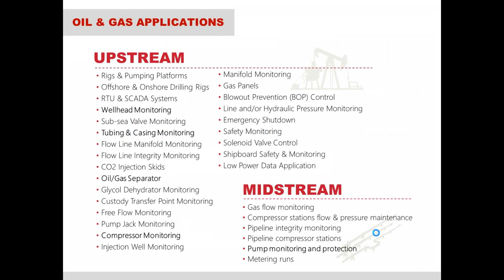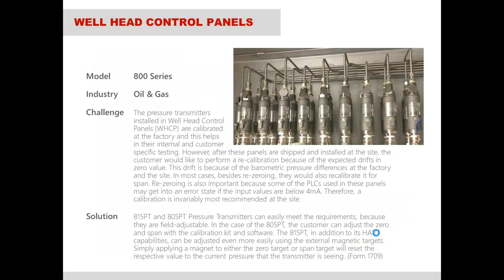Oil and gas is littered with different applications for the 800 series. I won't go through all of these through the upstream and midstream; I'll get into more of these application notes instead. Wellhead control panels are a big application where we sell a lot of pressure transmitters. As you can see here, a lot of different transmitters can be put into a very small area. For example, if you were to use a Rosemount 3051 with local indication and the traditional style housing, this box or container would have to be much, much larger to accommodate all those different pressure transmitters at that size.